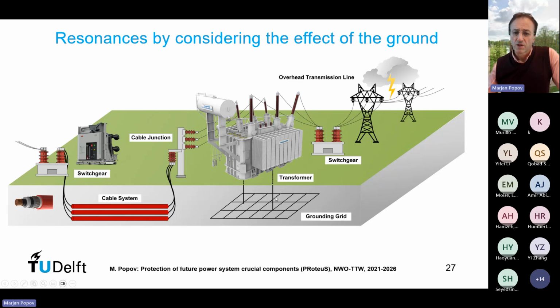A good grounding for 50 hertz may be a very bad grounding for higher frequencies, as the grounding impedance is far from zero and may show unpredictable effects that depend also on the soil structure. It is also very much dependent on where these transformer neutral points are grounded. So it is not the same if it is grounded like this or grounded differently here. We have a lot of if-then questions concerning this matter.